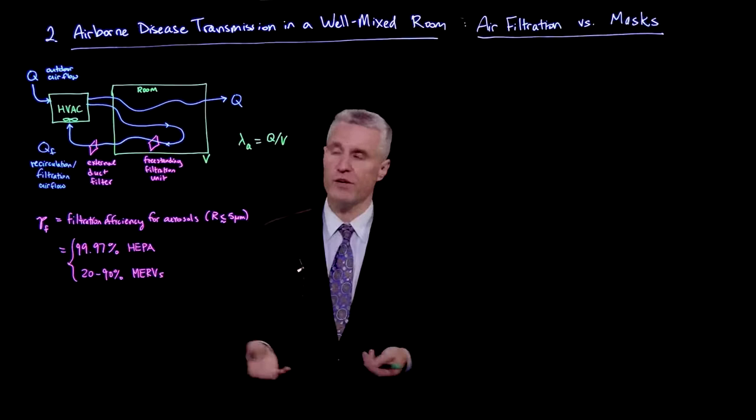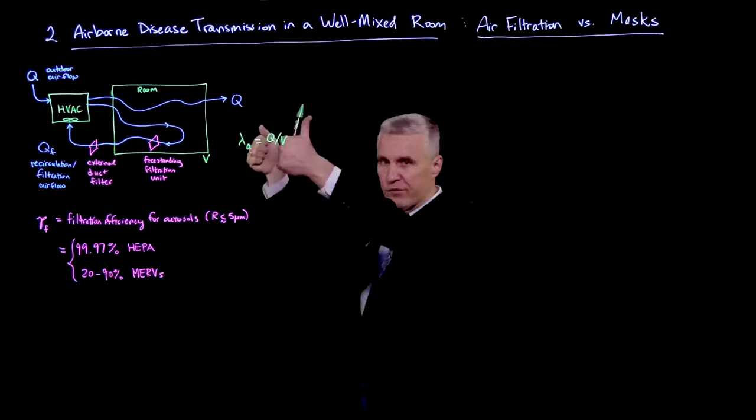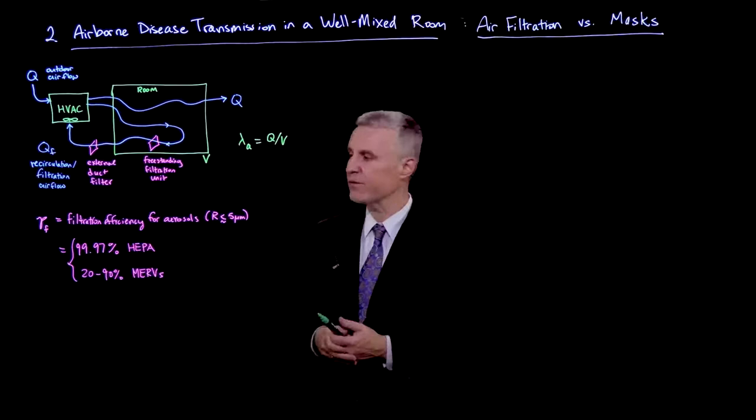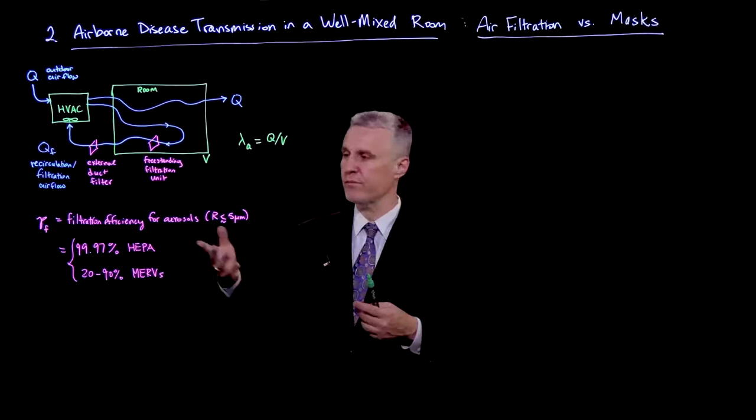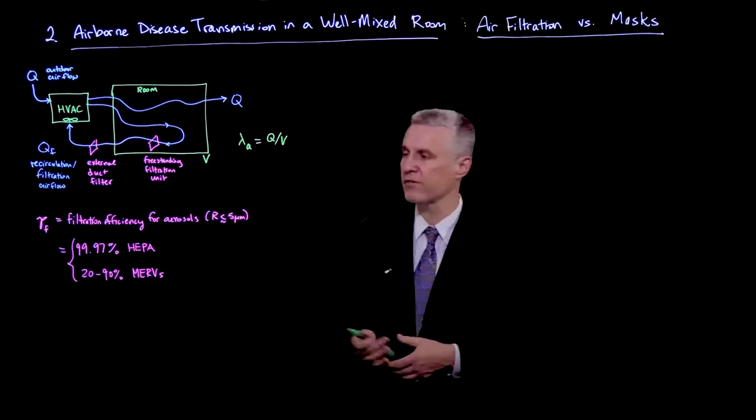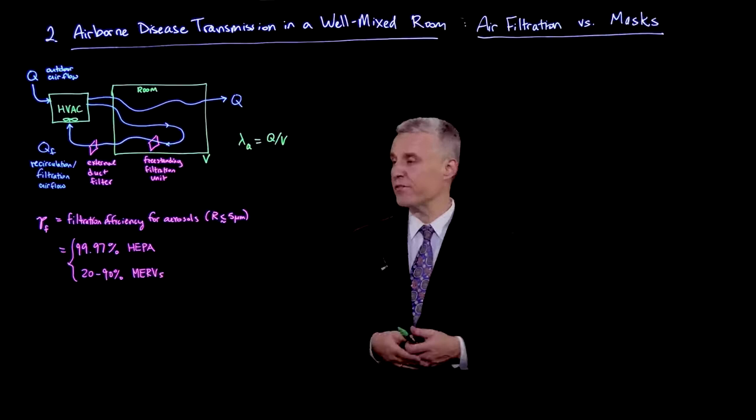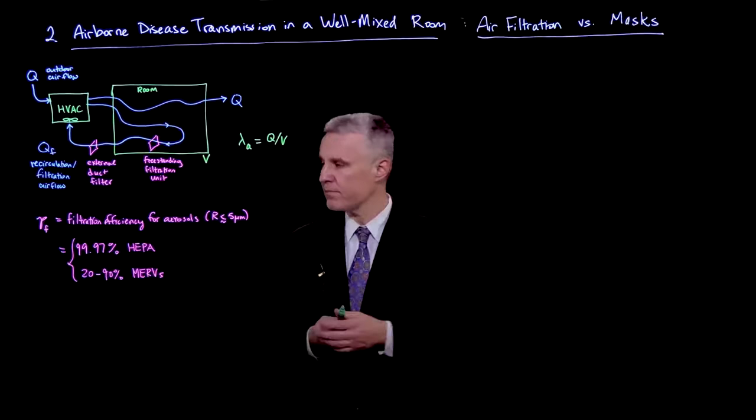Those filters typically are given MERV ratings, which are mean efficiency rating values. We're interested in the filtration of aerosols. If P_F is the fraction of aerosols that are blocked, for example, less than 5 micron radius, different ratings of filters give you anywhere from 20% to 90% filtration. A very high quality filter would be a HEPA filter, high efficiency particulate air filtration unit, which gives even as high as 99.97%.